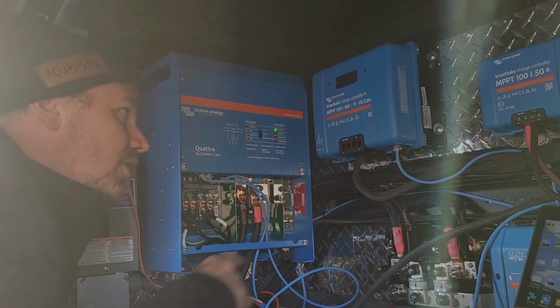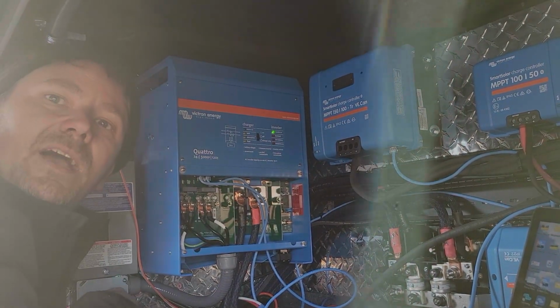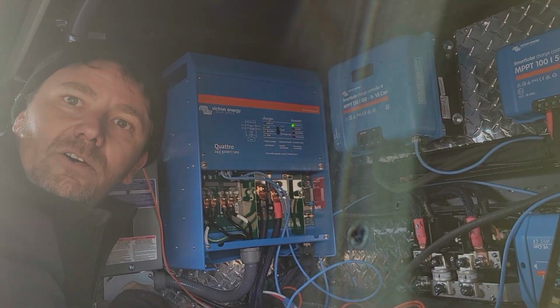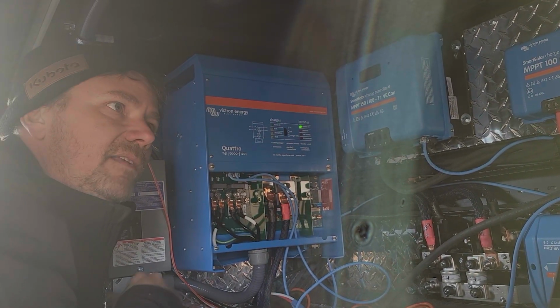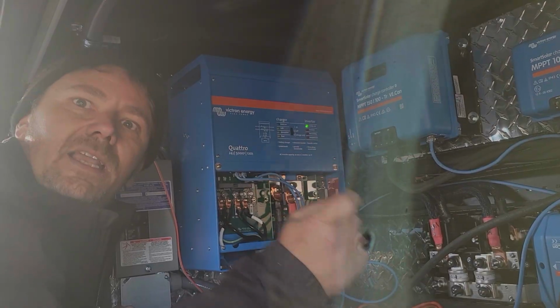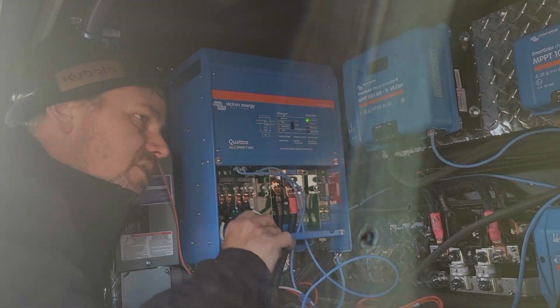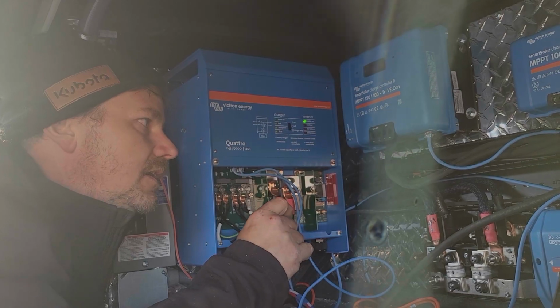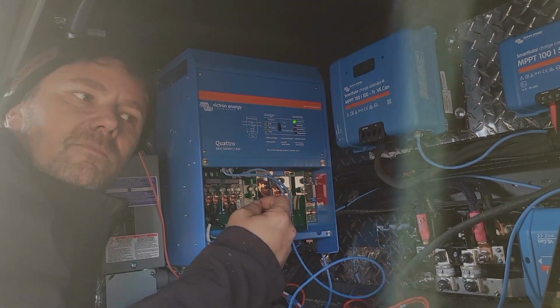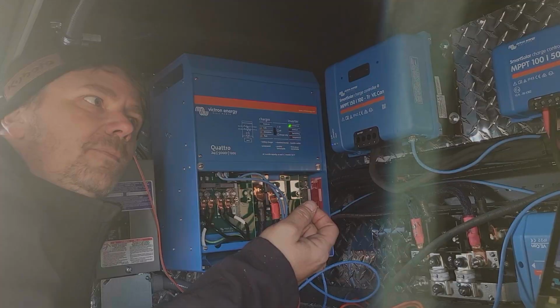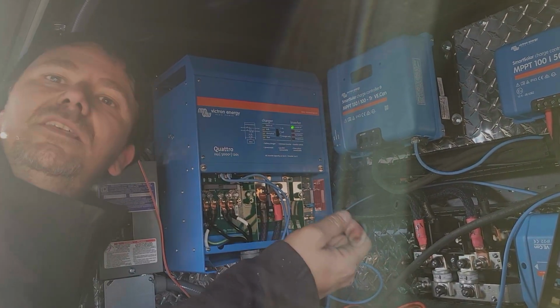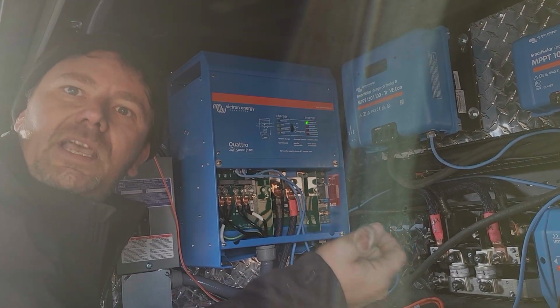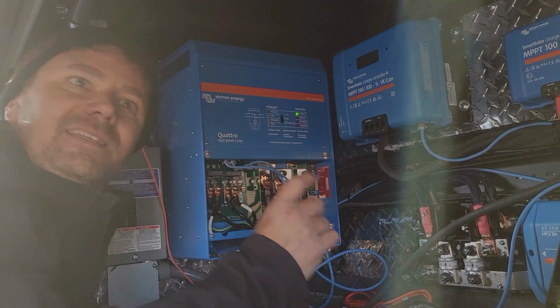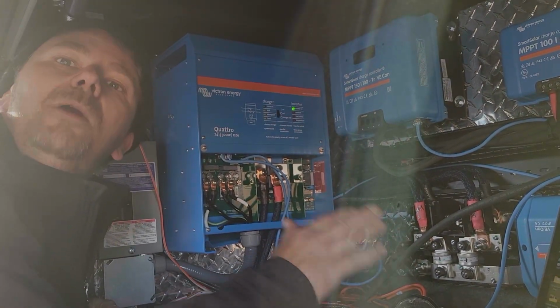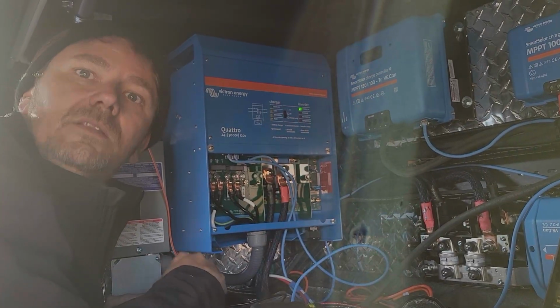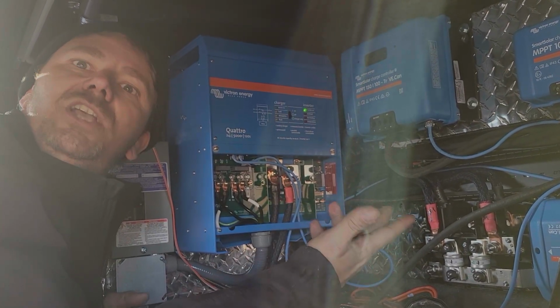By doing so, an MPPT tracking algorithm is constantly evolving. To get that maximum power point to track slightly faster, or to change the characteristics of the MPPT just slightly, that's what they're getting. By updating the firmware, they may be able to get you 0.1% more efficiency out of the tracking algorithm. Got it. That 0.1% is absolutely worth updating the firmware for. Right. So that's what their engineers are constantly changing.